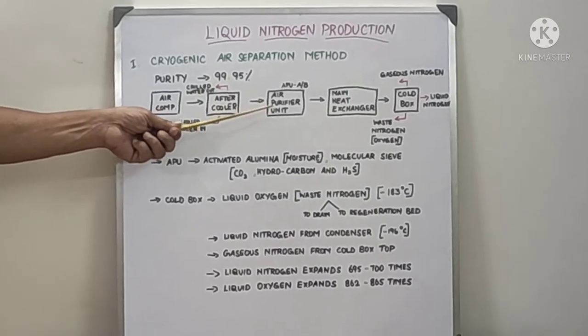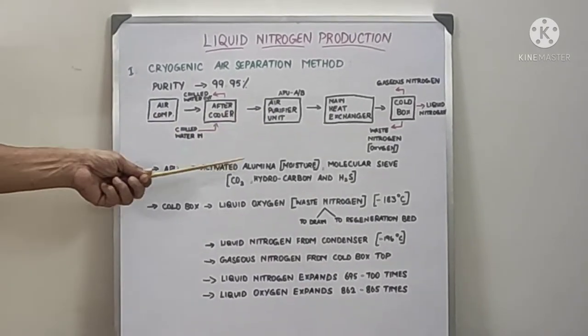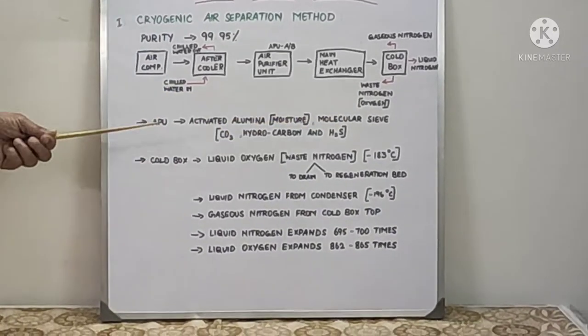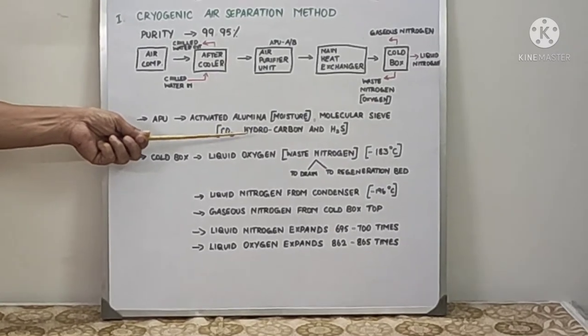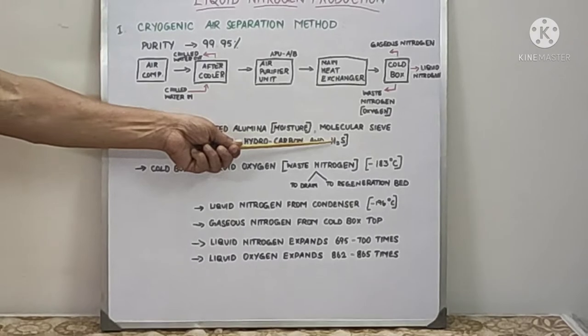Then it goes to the air purifier unit. The air purifier unit is filled with activated alumina to remove further moisture and molecular sieve, which is used to remove carbon dioxide, heavy hydrocarbons, and hydrogen sulfide.